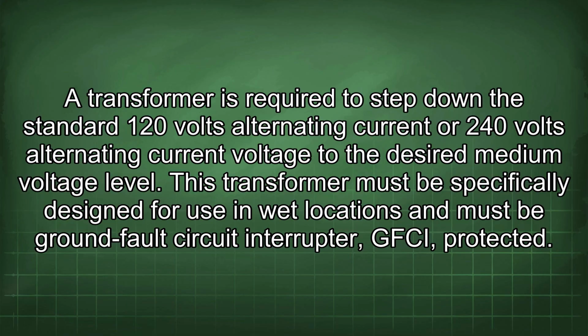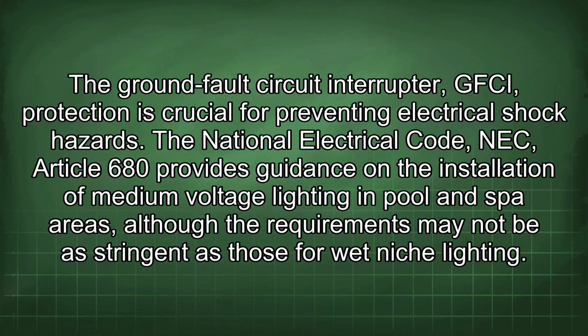A transformer is required to step down the standard 120 volts alternating current or 240 volts alternating current to the desired medium voltage level. This transformer must be specifically designed for use in wet locations and must be ground fault circuit interrupter (GFCI) protected. The GFCI protection is crucial for preventing electrical shock hazards.